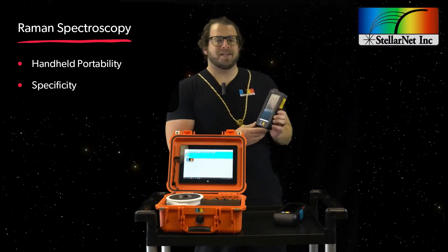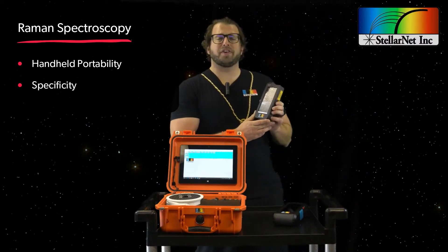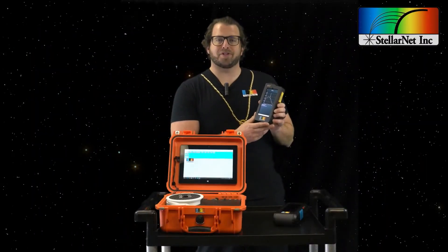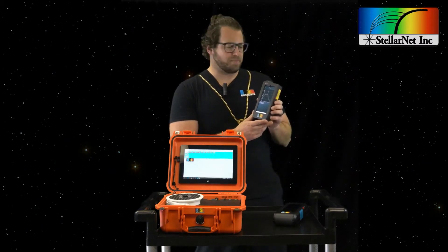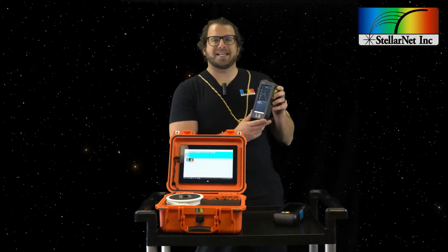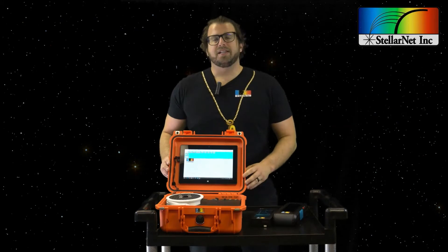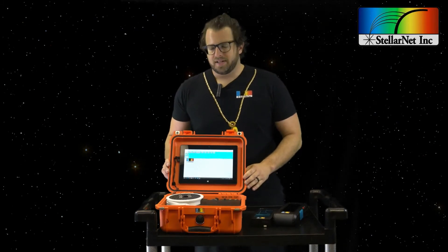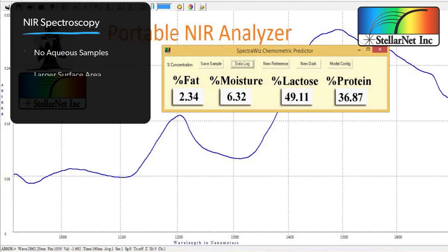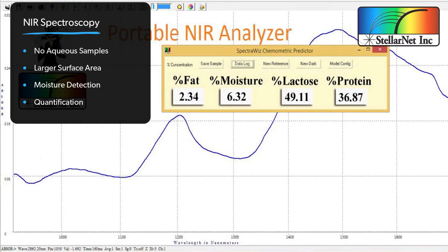Another benefit of Raman spectroscopy is specificity. In a Raman spectrum you have sharp, finger-like emission peaks which are representative of a molecule. When you have mixtures of molecules, you can easily identify each molecule by its sharp emission lines. This means you don't have to have all the samples and all the mixtures in your library database in order to get spectral matches.